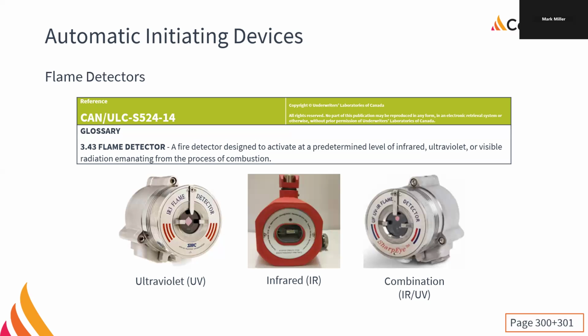So we had flame detectors on the fire alarm system, and we had flame detectors tied into the electrical panels. The electrical panels that we installed to power all the lab stuff was on a contactor, and that contactor, well, there was e-stops on it, but it was also the flame detector. So if you stood in the middle of the room and just flicked the Bic lighter, it would shut off all the power in the room. It was pretty cool. And then years later, I was all grown up and old. I got to do flame detectors for airplane hangars because they detect flame.